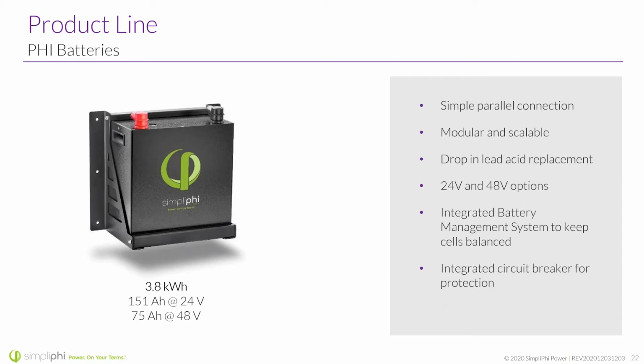Again, this is our standard Phi battery, our 3.8 kilowatt hour battery, 151 amp hours at 24 volts, 75 amp hours at 48 volts. So we do have the option of 24 or 48. You are not going to put these in series ever. If you want 48 volt batteries, you get 48 volts and parallel them. If you want 24 volts, same thing—we don't put two 24 volts in series to get 48 volts with these.